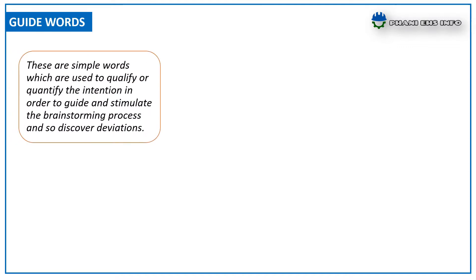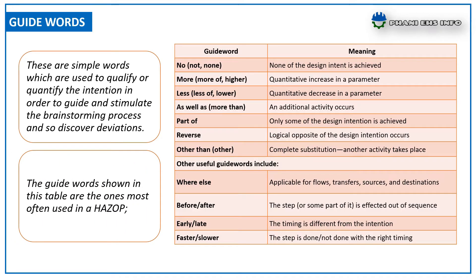Before discussing the examination phase, let us look at guide words. These are simple words used to qualify or quantify the intention in order to guide and stimulate the brainstorming process and discover deviations. The guide words include: NO — none of the design intent is achieved; MORE — quantitative increase in a parameter; LESS — quantitative decrease in a parameter; AS WELL AS — an additional activity occurs.